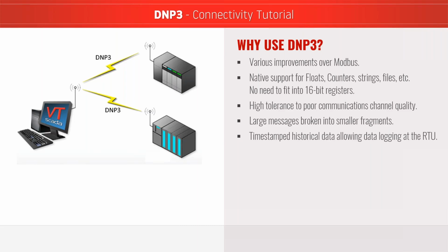With DNP3, everything is timestamped when it comes in, and there's the ability to read many different pieces of data at once through a larger historical time period. So with the timestamped data, you don't have to poll the device as often, but you can still get very high data resolution, and it can be backfilled into your history as it was seen by the device.